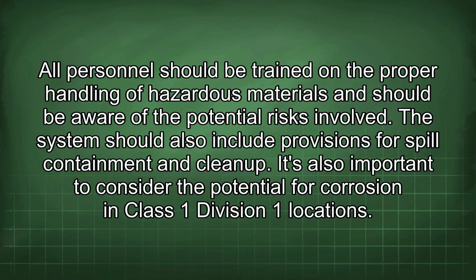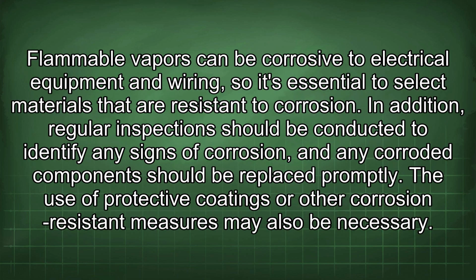It's also important to consider the potential for corrosion in Class 1 Division 1 locations. Flammable vapors can be corrosive to electrical equipment and wiring, so it's essential to select materials that are resistant to corrosion. In addition, regular inspections should be conducted to identify any signs of corrosion, and any corroded components should be replaced promptly. The use of protective coatings or other corrosion-resistant measures may also be necessary.